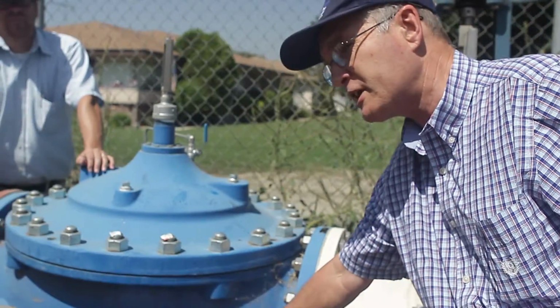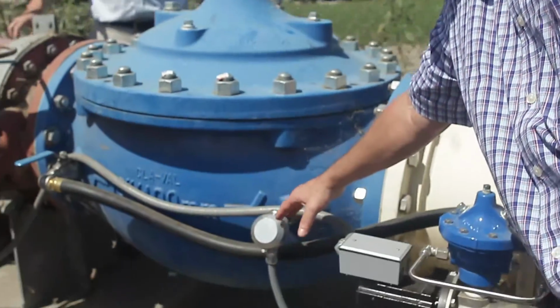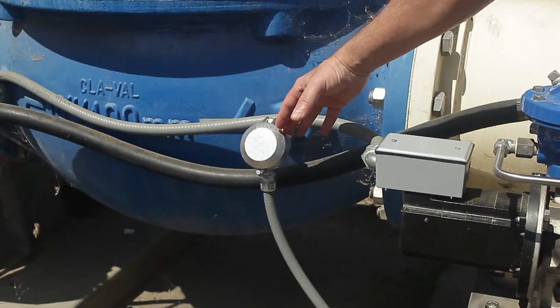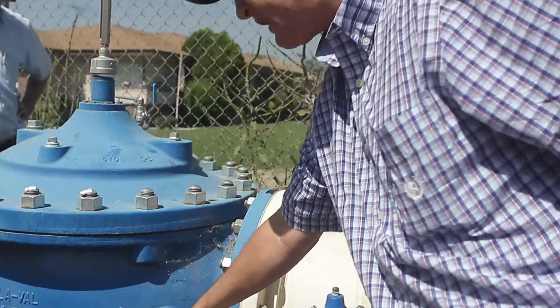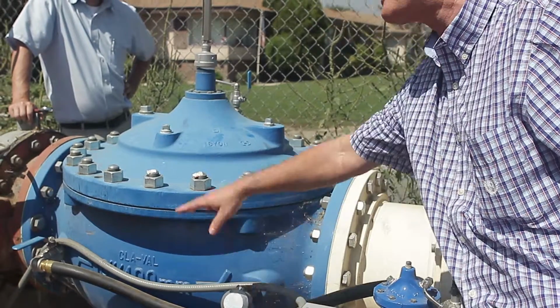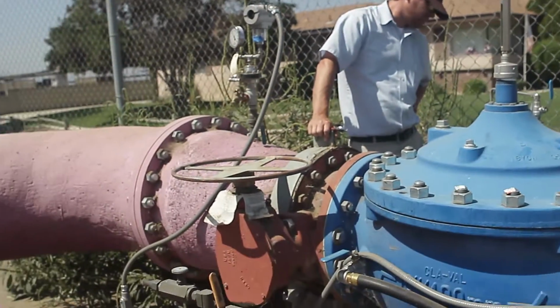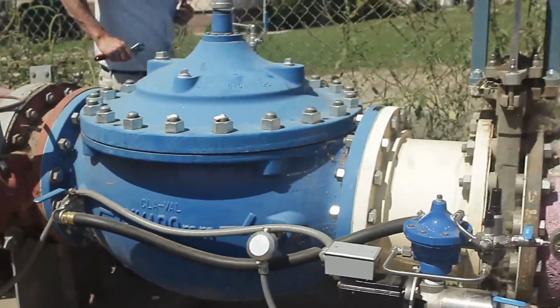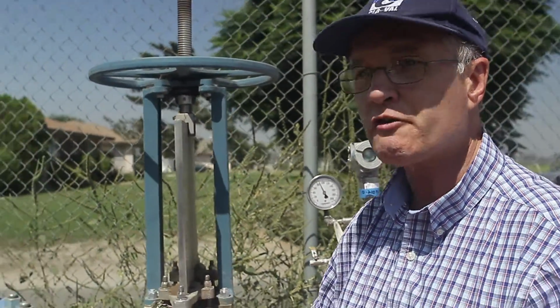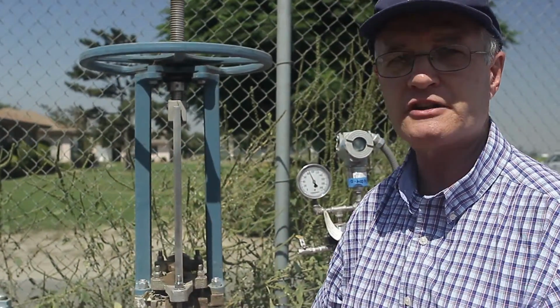Right here on the valve, as Jeff mentioned, the flow meter itself is very low power. It's only 4 to 20 milliamps, loop powered, so it's a very low power requirement. And it's a 2-wire transmitter, just like these pressure transmitters, so it's a very simple device. So we'll now go over to the panels and describe the electrical equipment.